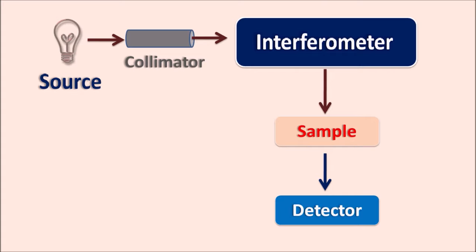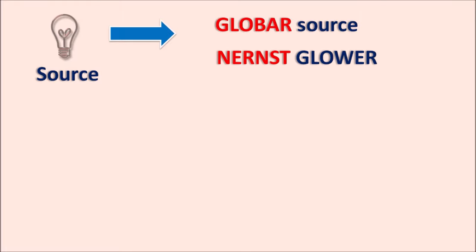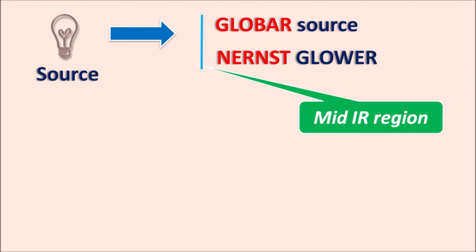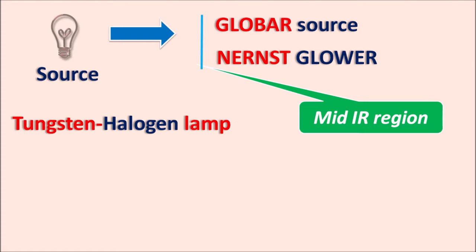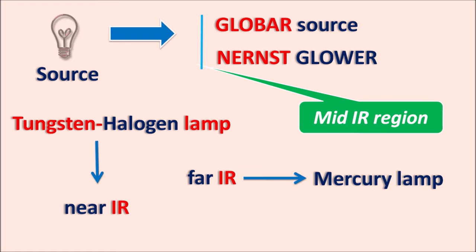After passing through the interferometer, the transmitted radiation comes perpendicular to the interferometer, is transmitted into the sample, and finally reaches the detector. For the source, we generally use the mid-IR region, for which we can use the Globar source as well as the Nernst glower — both useful in the mid-IR region from 4000 to 400 cm⁻¹. A tungsten halogen lamp is used for the near-IR region, and a high-pressure mercury vapor lamp is used for the far-IR region.